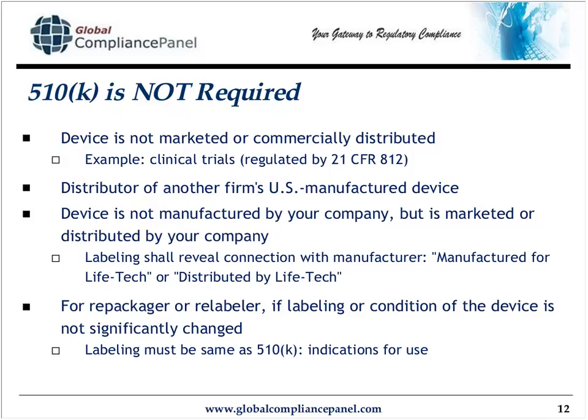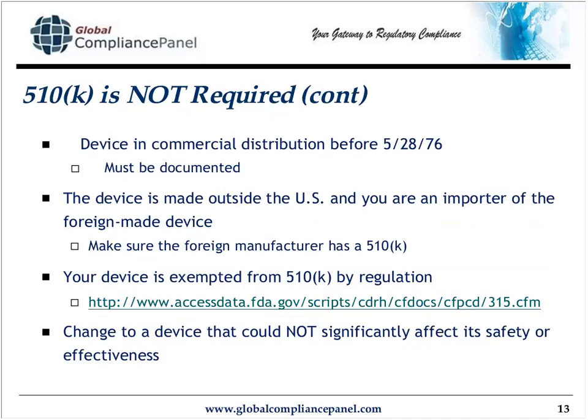For firms that repackage and relabel, contrary to the earlier examples, there are situations in which the labeling or condition of the device is not significantly changed. For example, if the labeling is the same, no 510K is required. Also, if you have a device that's been in commercial distribution since before May 28th, 1976, the pre-amendments devices, as we call them, a 510K is not required.